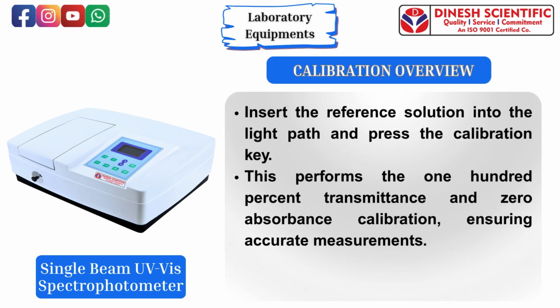Calibrating with reference. Insert the reference solution into the light path and press the calibration key. This performs the 100% transmittance and 0 absorbance calibration, ensuring accurate measurements.